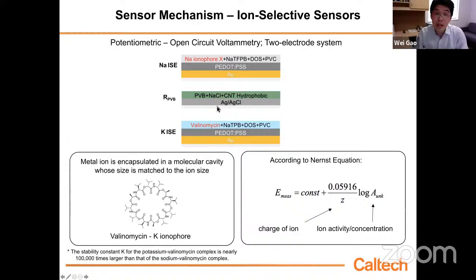According to the Nernst equation, the measured voltage difference between the two electrodes can be expressed with a log-linear relationship to the ion concentration. The slope is about 59.16 millivolts per decade of concentration for sodium and potassium, because the charge of the ion, Z, equals one. If you want to monitor magnesium or calcium, where the charge of the ion equals two, the slope or sensitivity becomes roughly 29.6 millivolts per decade of concentration.